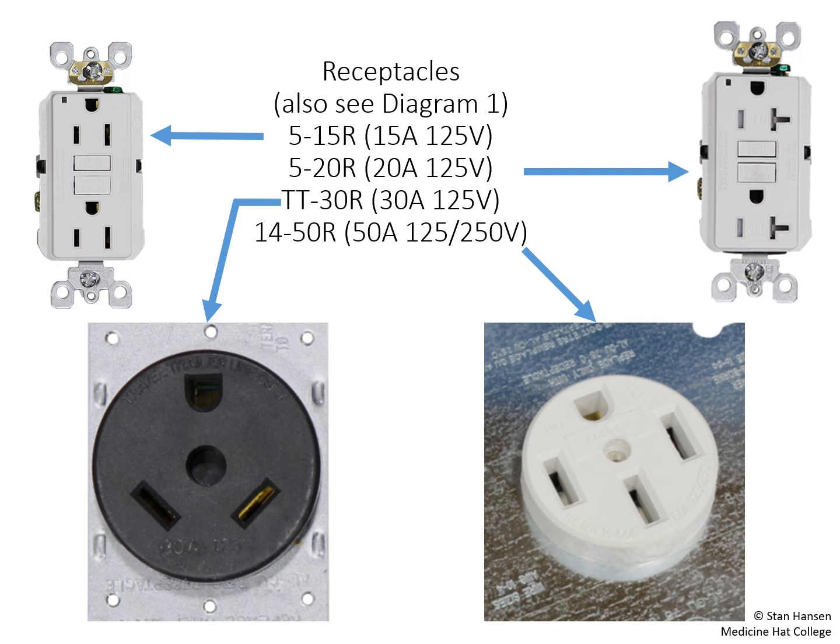When it comes to mobile homes, according to Rule 72-108, the connection must be permanent unless there's a deviation that allows for it to be connected to a 14-50R receptacle, but that's not very common because it's a very small service. We need to make sure that when we install them vertically, we place the U-shaped bonding post on the top of the outlet. You'll find that most of the cords that are built for RVs will also have that ground terminal on the top of it, and then it will hang down from that point.